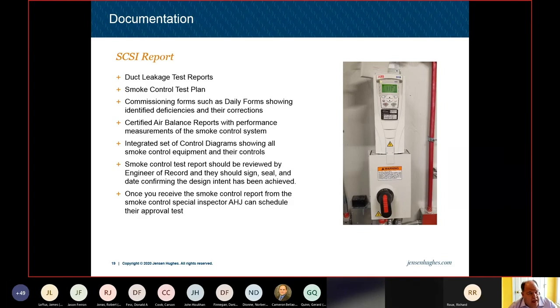Also included is the commissioning form, such as the daily form showing all the identified deficiencies and their correction. There could be a whole lot of deficiencies identified and corrected, but it shows the evolution of the system coming together. Then the certified air balance reports, with the performance measurements of the smoke control system. That's from your certified air balance contractor, and they're measuring stair pressurizations, atriums, fan performance. There's a lot of different things that go into it.